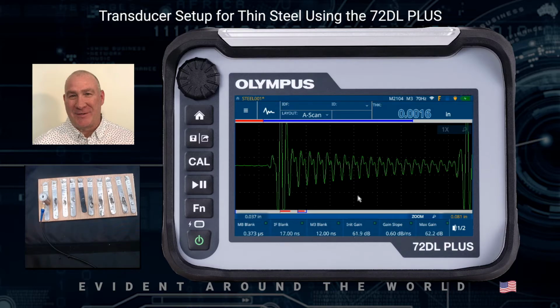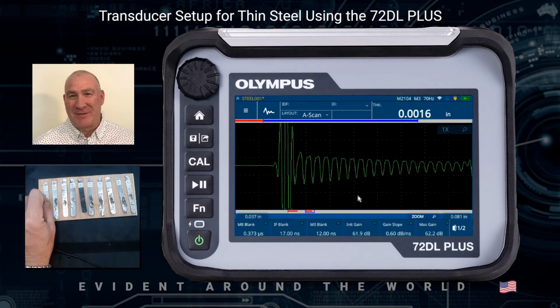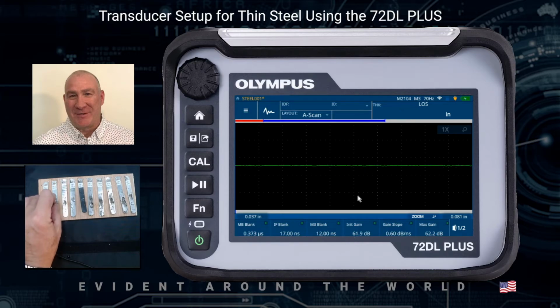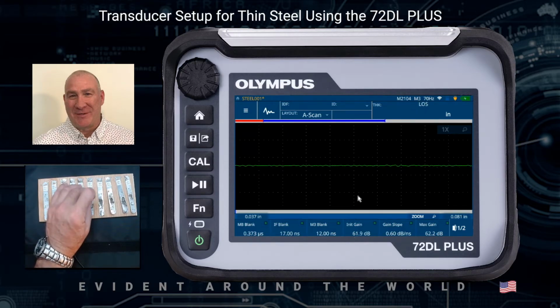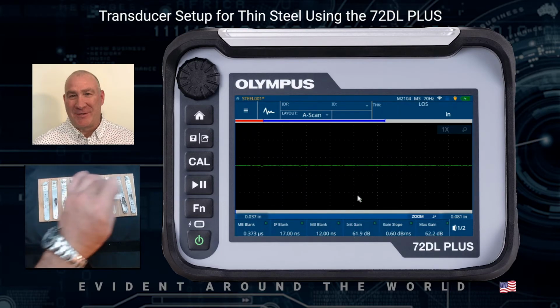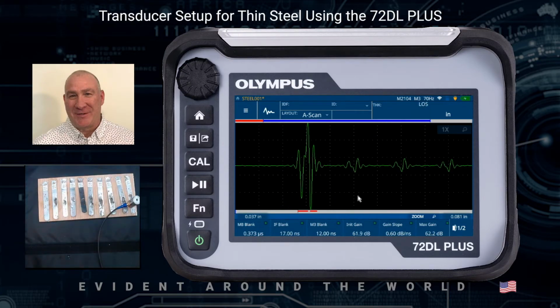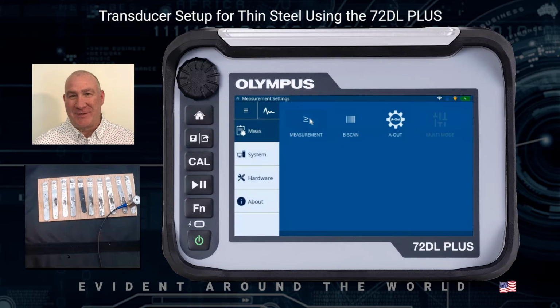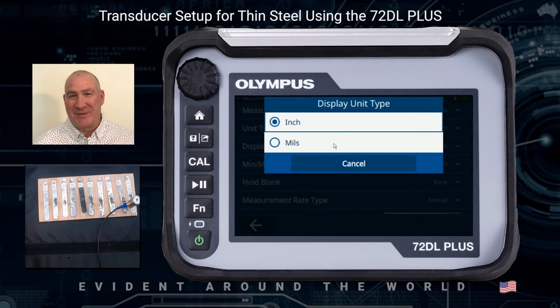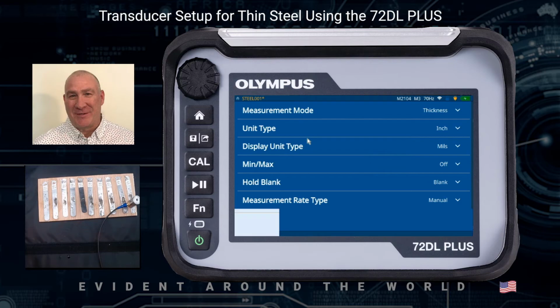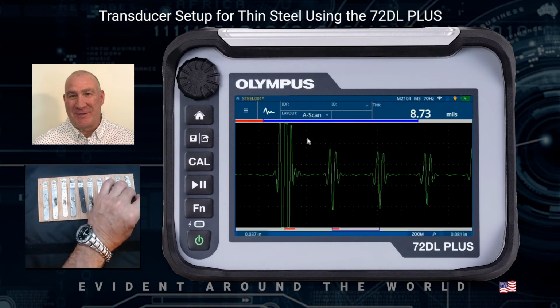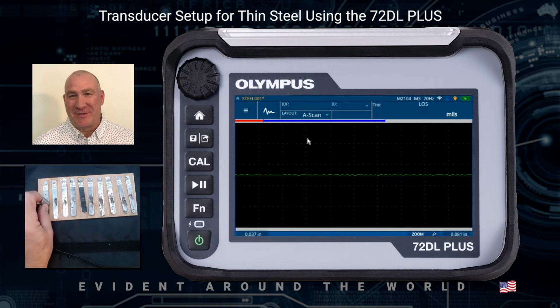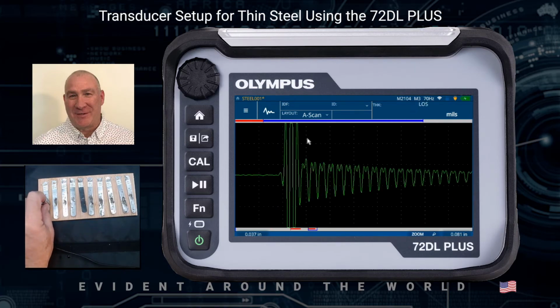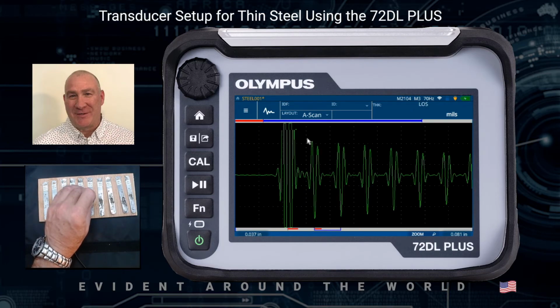So I'm going to unfreeze this by hitting the pause play key, which is under the cal key again. I'm going to go back and couple, and it's supposed to be reading 1.5. It's reading pretty close. Let me go to something in the middle here. It's supposed to be 5 thousandths. It's reading 4.9. And this is supposed to be reading about 9. So just to make it easier, I'm going to go into my setup and settings, go to measurements, and change my units to mils. Okay, and then I can hit the home key under the knob to go back. Now I'm displaying my measurement in mils. You can see it's reading 8.73. This one is reading about 1.6, 1.6, so it's off a little bit. And my 5 is reading pretty close to 5.